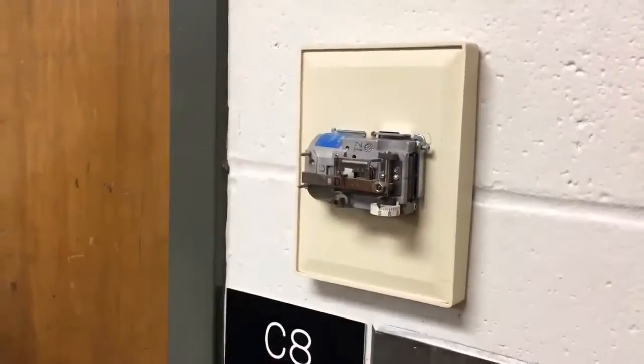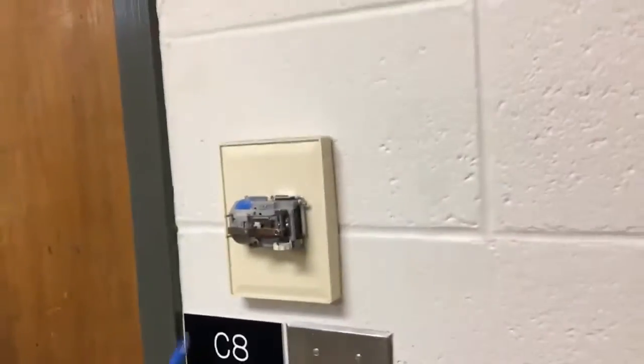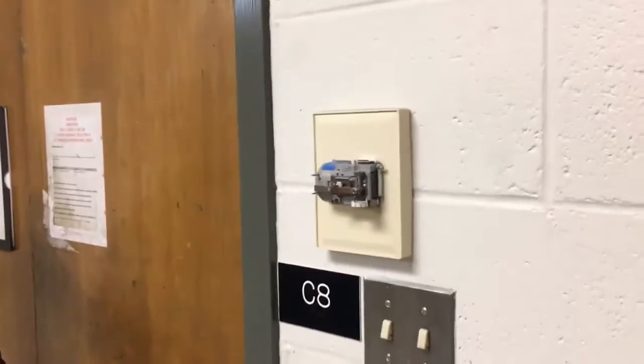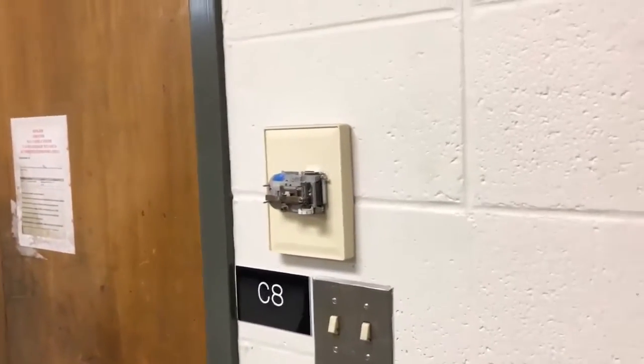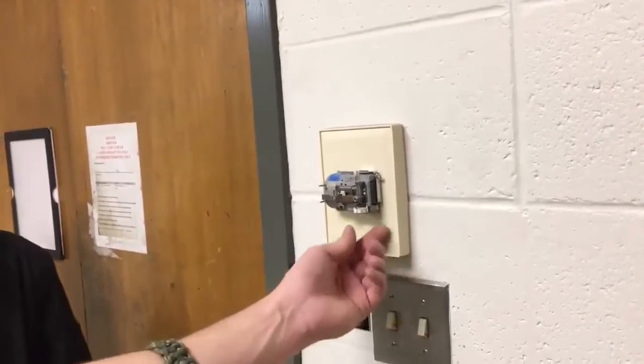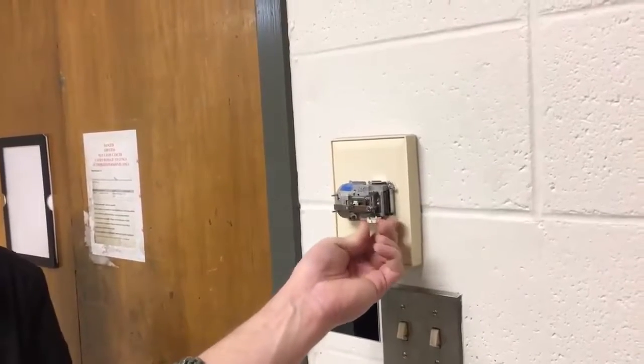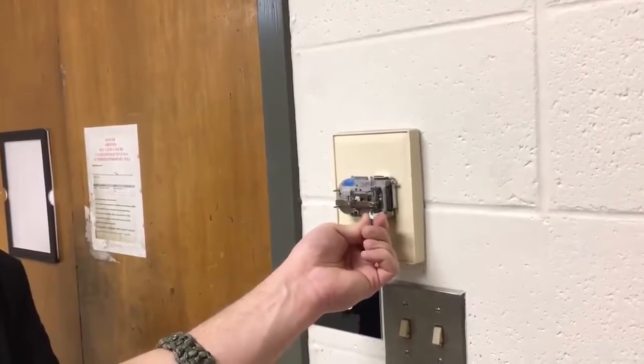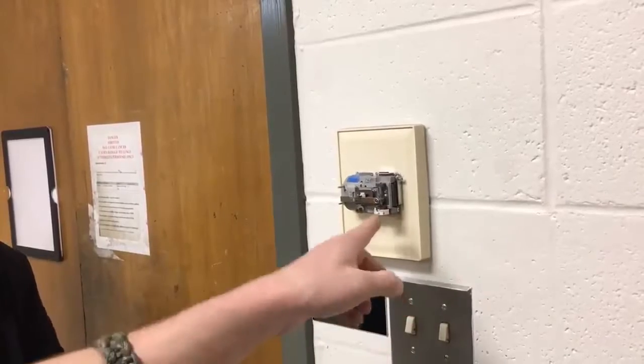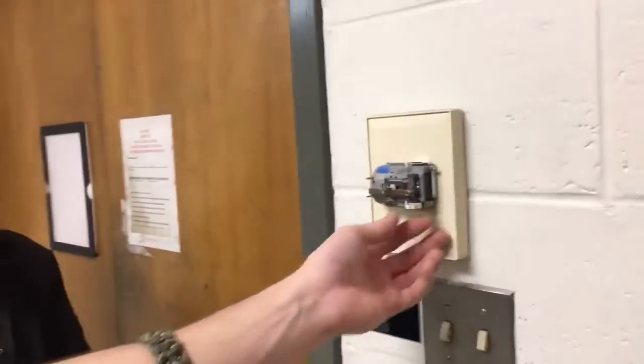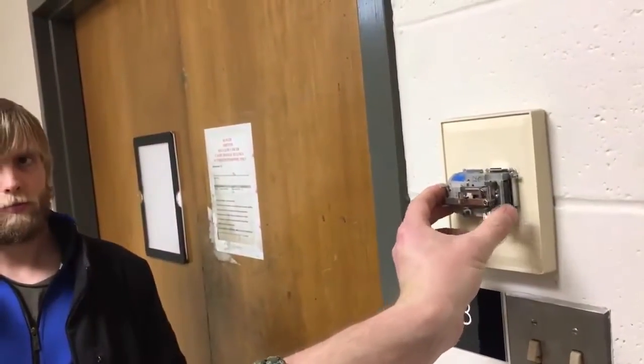And then just to check your calibration, you've got to kind of step away for a little bit, because that metal strip's very sensitive. Your body heat will make it flex. So after you've stepped away for a couple minutes, you can come back, turn this dial, and there you started venting pressure at about 78. So it's closer. I say if you can get these within a degree or two, that's good enough.